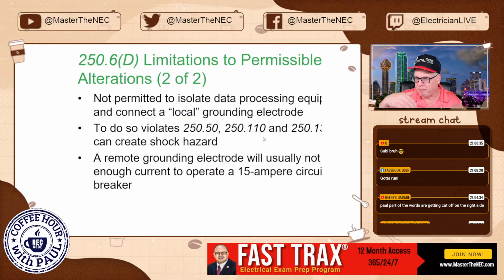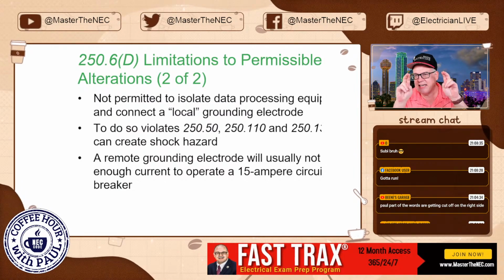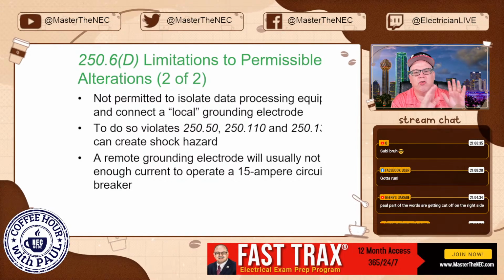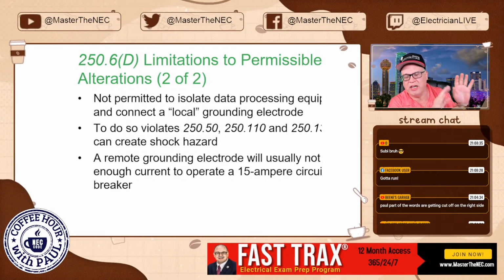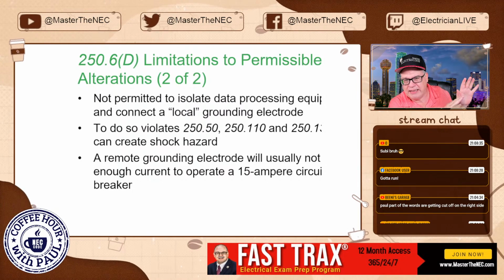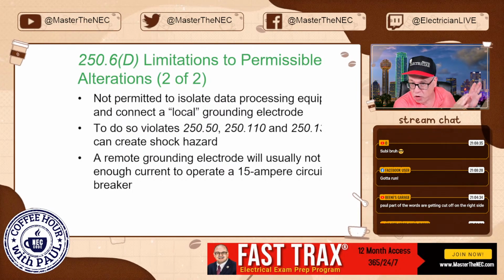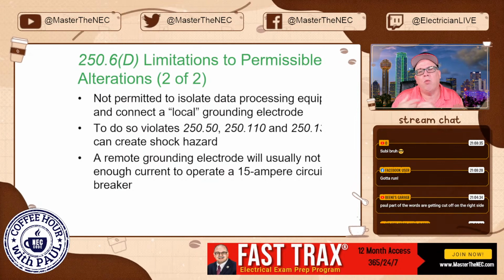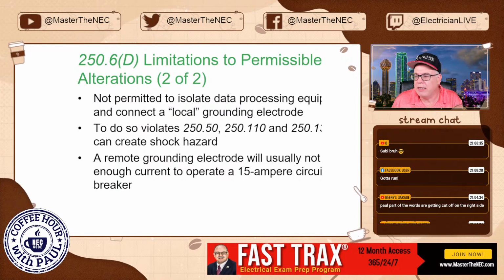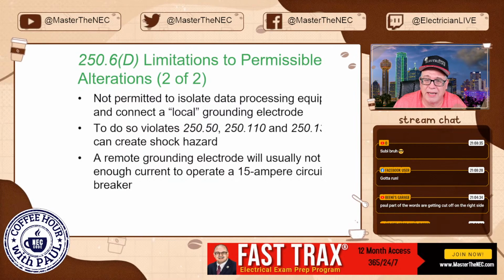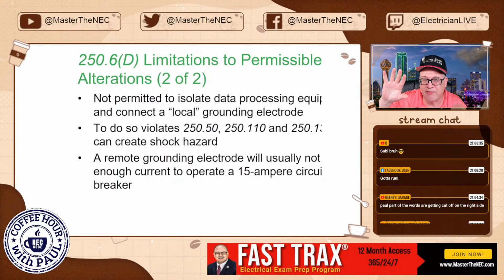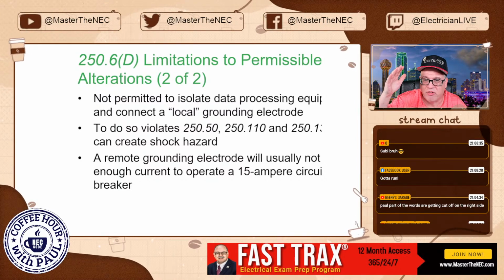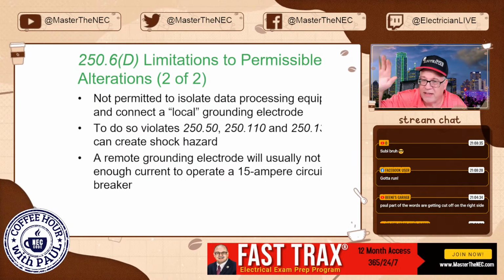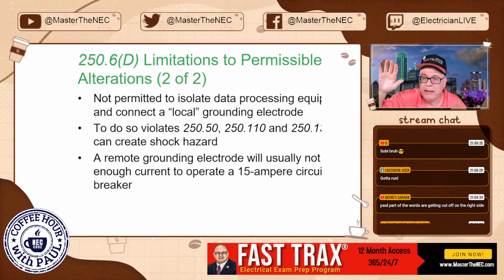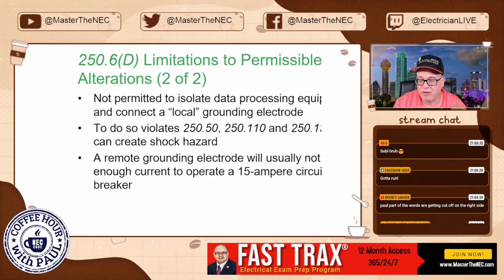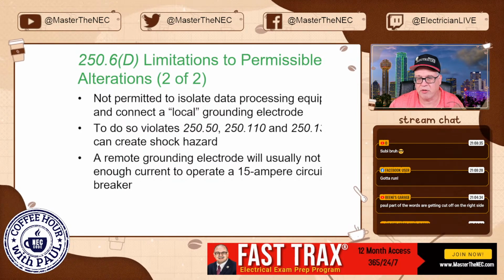So in other words, if I had a piece of equipment and they want a clean connection, they can't say, well, I don't want you to run any connection to the system. I don't want an equipment ground. I don't want any connection to anything that might be connected back to that source connection. I want to have my own electrode here. You know what? You drive the electrode if you want. That's an auxiliary. It has no rules you have to follow. It doesn't matter whether they want to run 14 gauge to it. Okay? It's just something that they want. It's in addition. Go for it. But it is not to take the place of the required equipment grounding conductors and all that kind of stuff, okay?